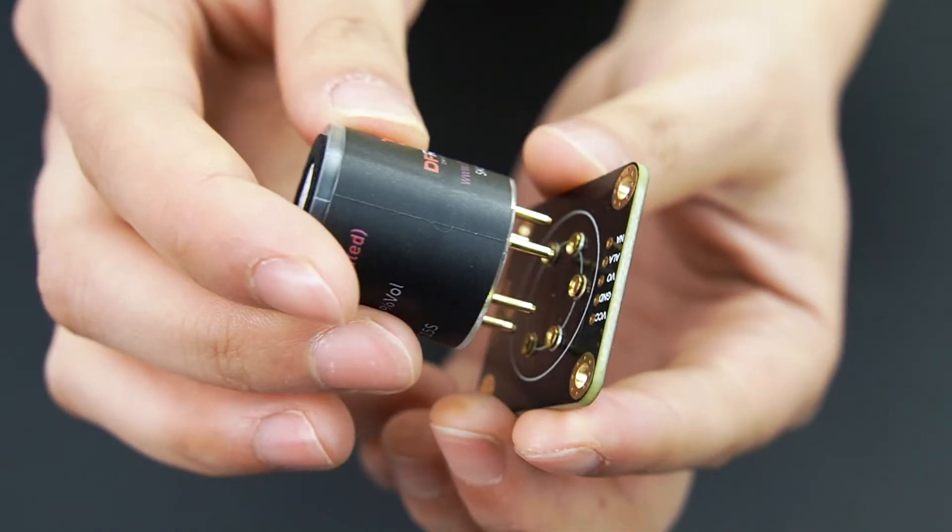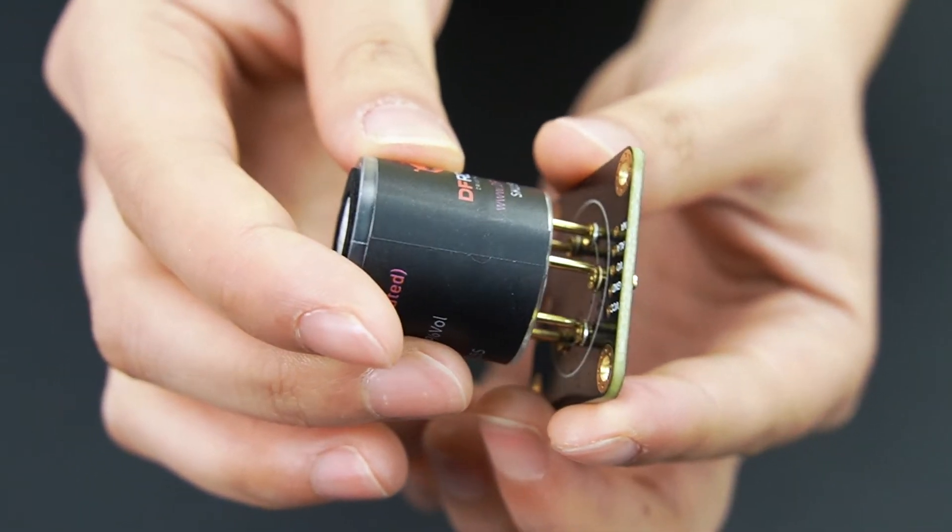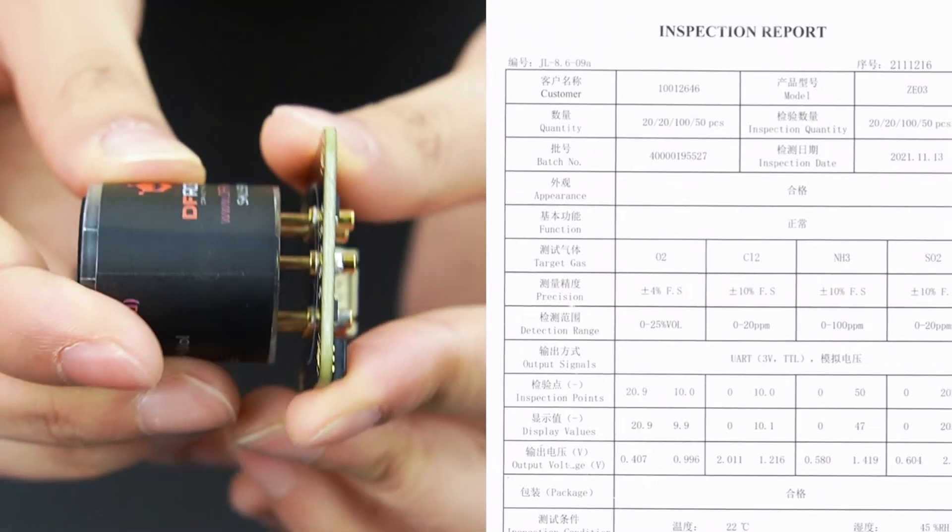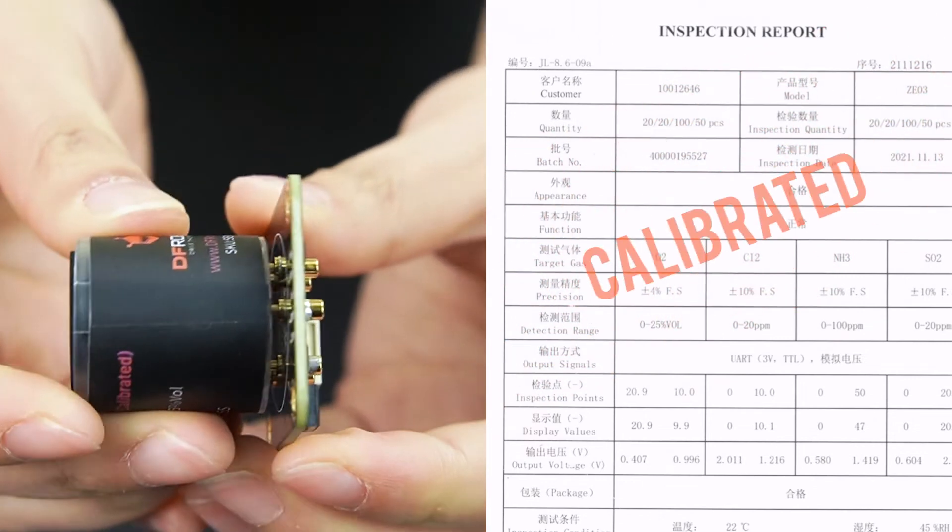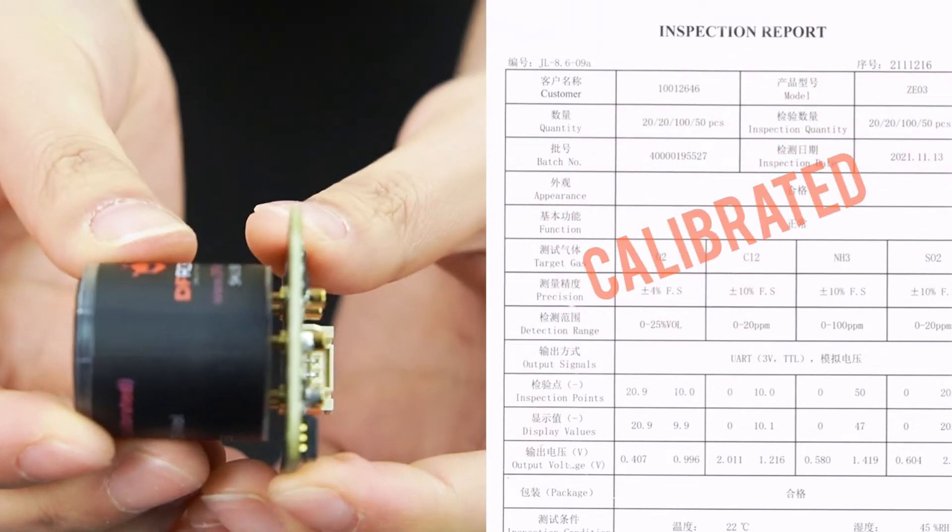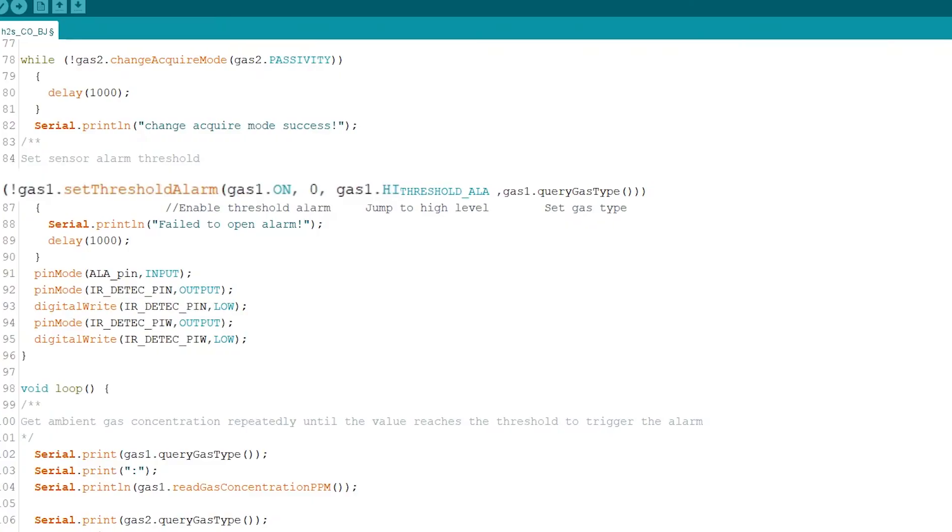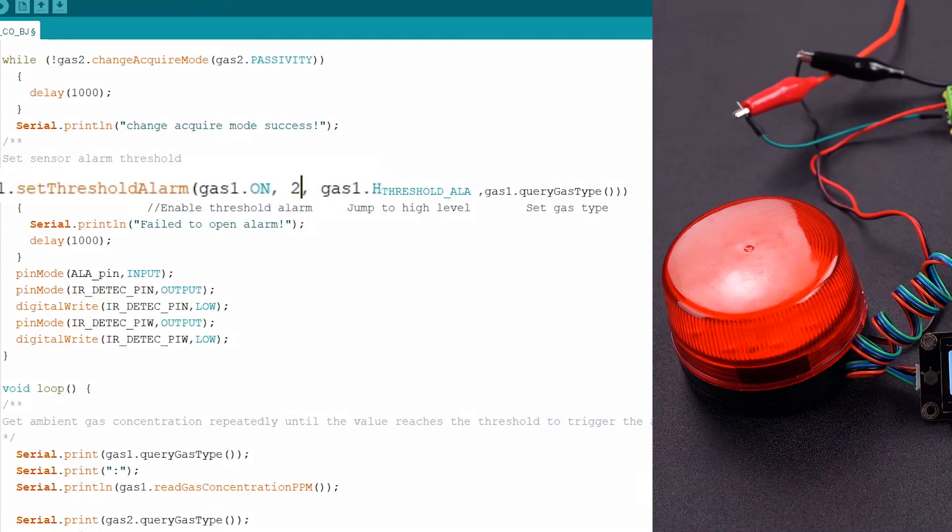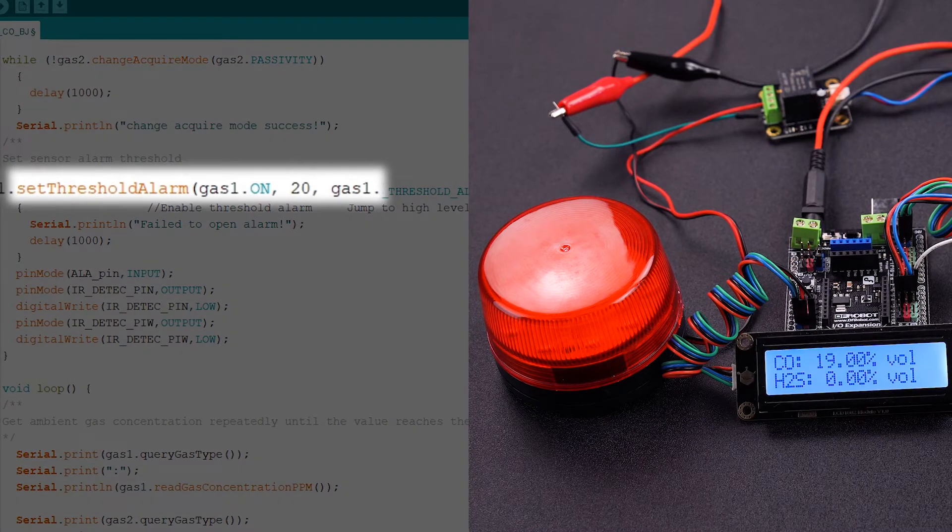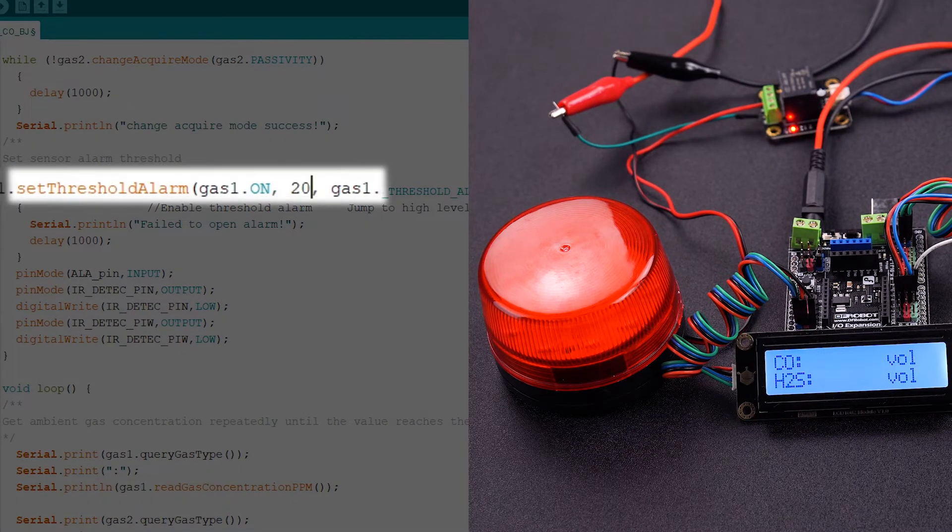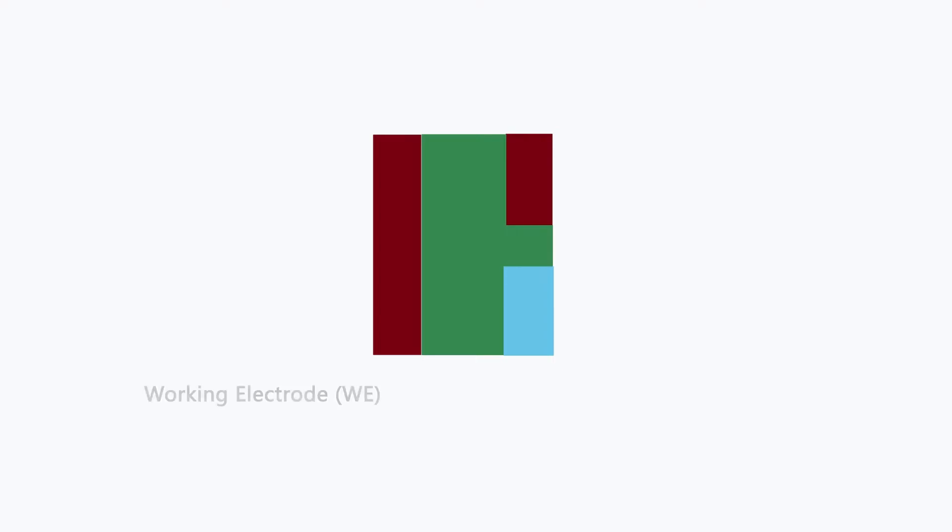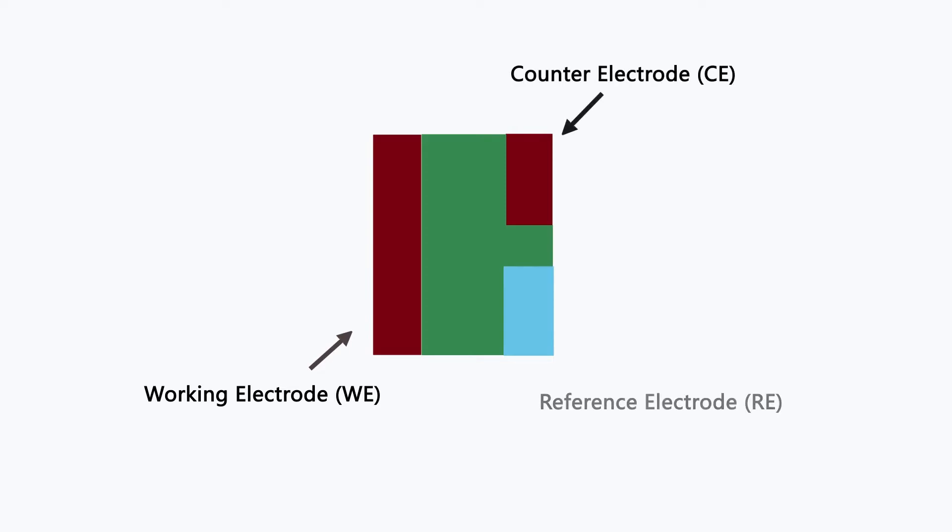Of course, like the previous oxygen sensors, all supported gas probes are factory calibrated. The sensor has a built-in threshold mode, which can be a gas alarm by setting the threshold. The electrochemical carbon monoxide sensor consists of three electrodes: working electrode, counter electrode, and reference electrode.